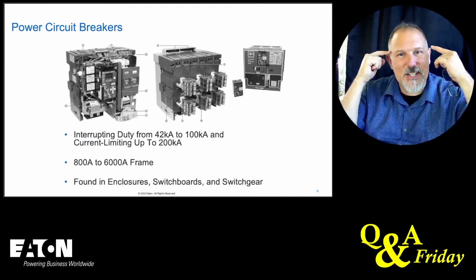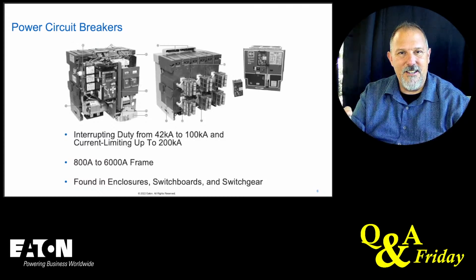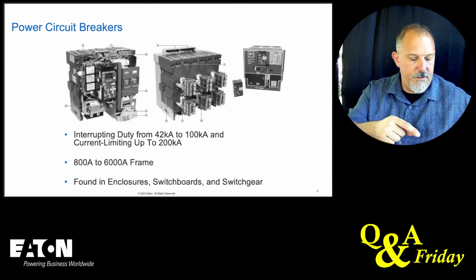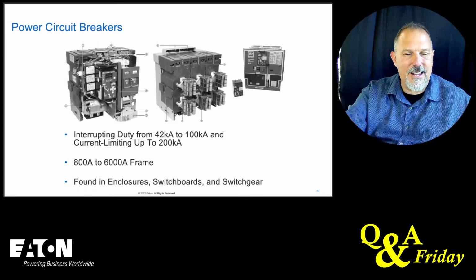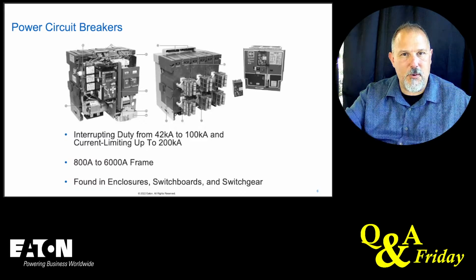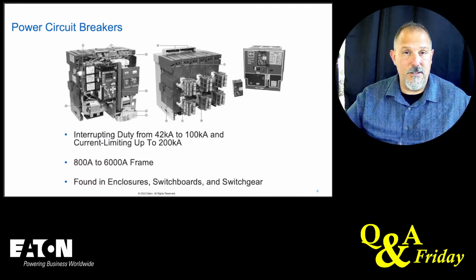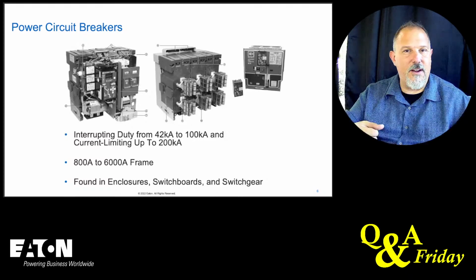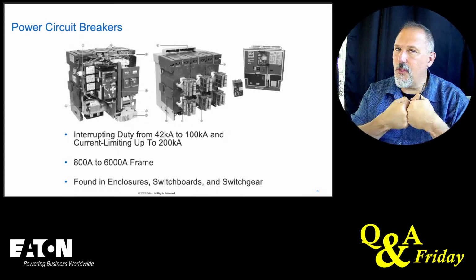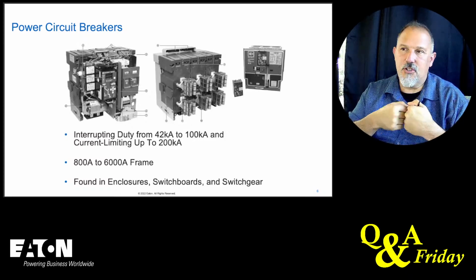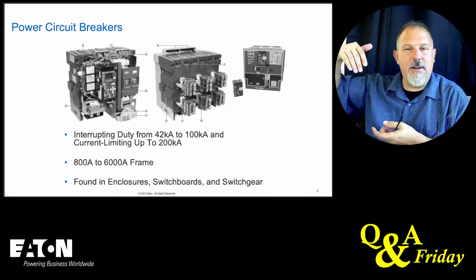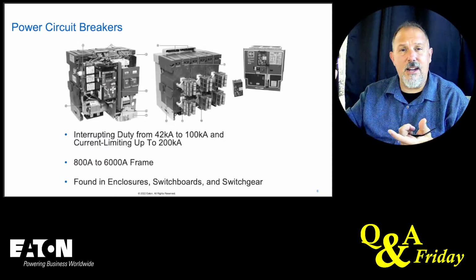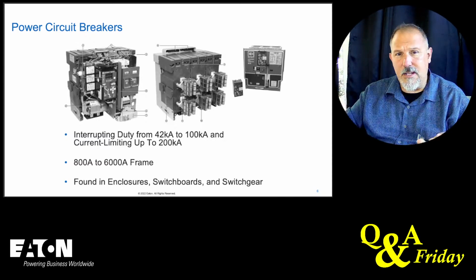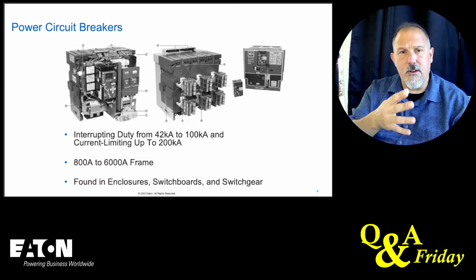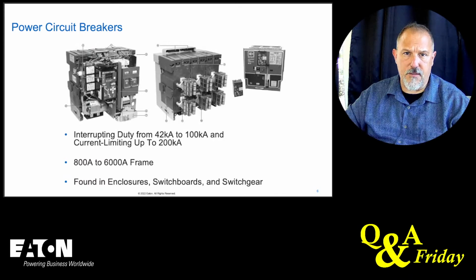And if you just understand that, the question of whether or not an insulated case circuit breaker or a power circuit breaker is current limiting should be answered. I'm not current limiting if I'm trying to hold my contacts closed for 30 cycles. So my power breakers and my insulated case circuit breakers, by their design, are not current limiting devices. You're going to get current limitation in your smaller overcurrent protected devices.